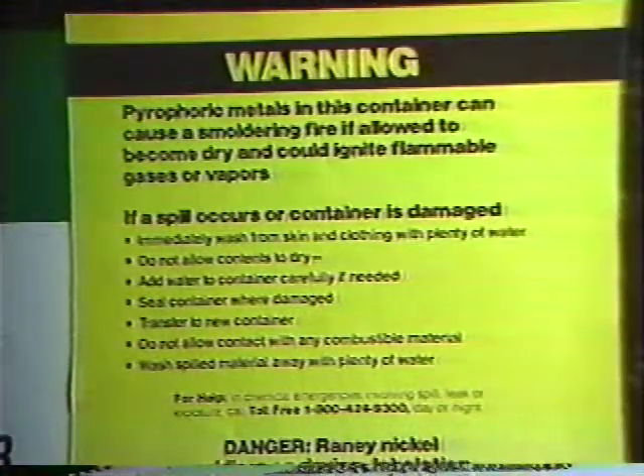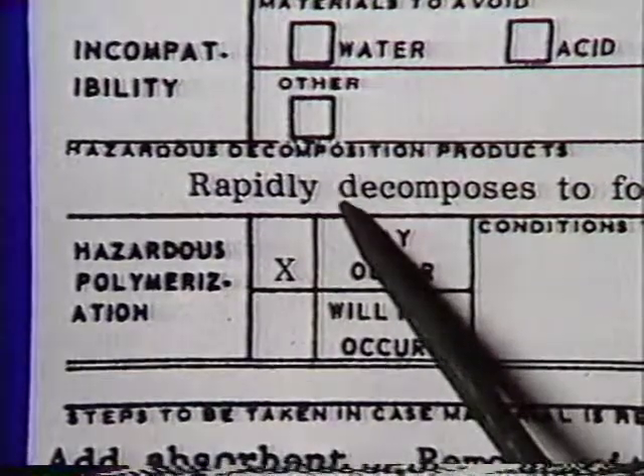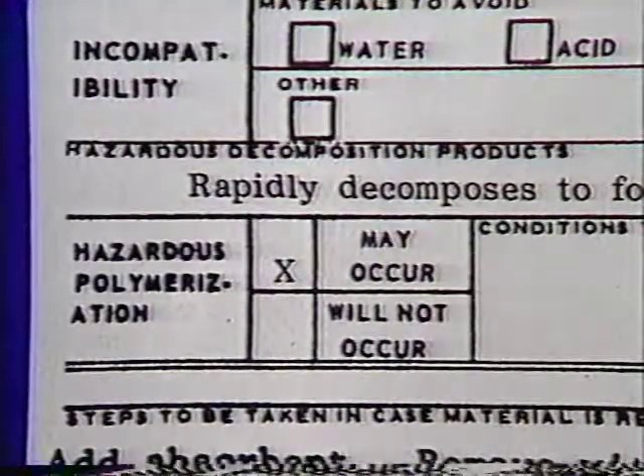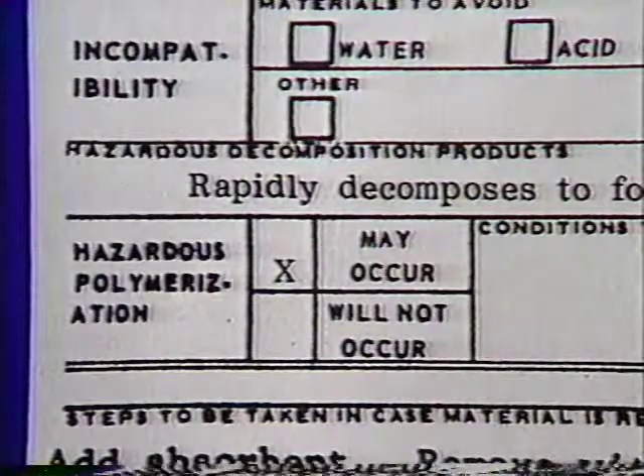Pyrophoric chemicals, or pyrophores, spontaneously ignite — that is, catch fire by themselves. They react so fast to the oxygen in the air that they generate their own heat. Some have so much energy they'll react with almost anything. When you see words like rapidly decomposes, polymerizes, or condenses on a material safety data sheet, you'll know that the chemicals can give off enough heat to start their own fires or keep them going once they've started.